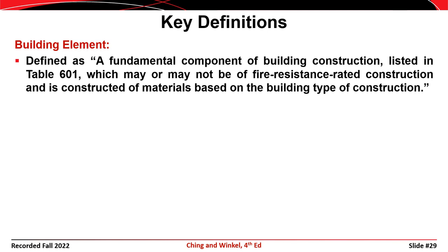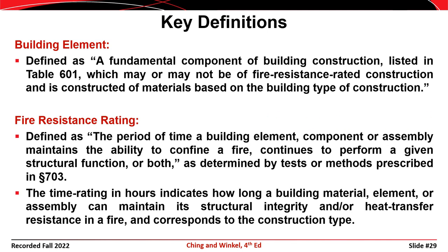A building element is defined as a fundamental component of building construction, which may or may not be a fire resistance rated construction, and is constructed of materials based on the building type of construction — it sounds rather circular. A fire resistance rating is defined as the period of time a building element, component, or assembly maintains the ability to confine the fire, continues to perform a given structural function, or both, as defined in IBC Section 703. The time rating in hours indicates how long a building material element or assembly can maintain its structural integrity and heat resistance in a fire.